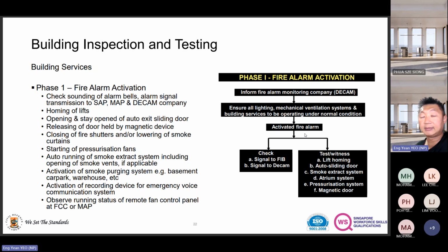All this will be taken by the QP, and we just need to verify not more than 110 Newton positive pressure within the staircase. The magnetic door, whether it can be released - if it cannot, we need to activate a bypass to release the door, because when there's no power supply, the door really needs to be bypassed so you can open up the exit door to go out from your tenanted space.